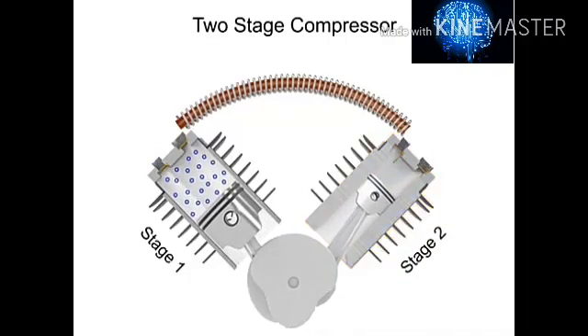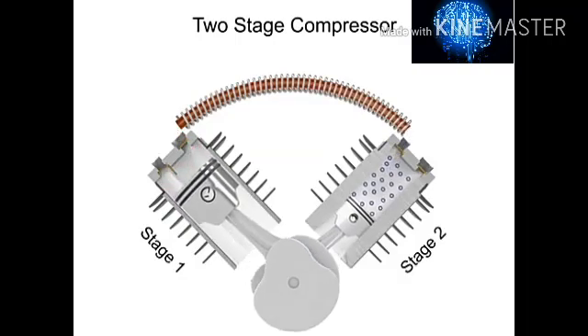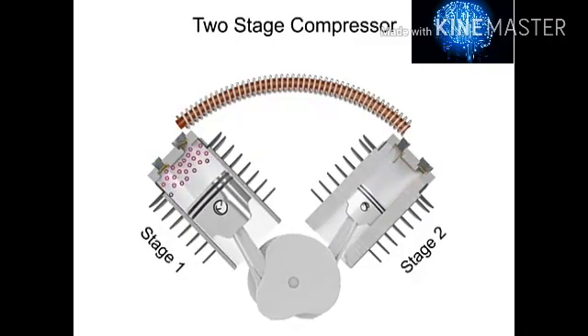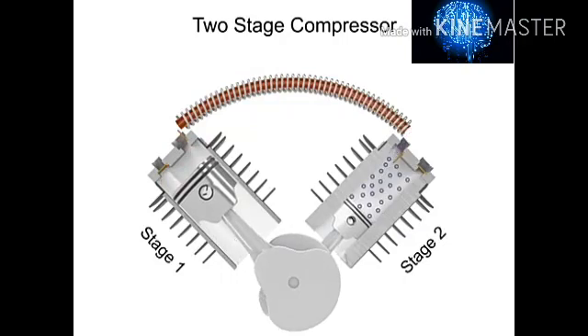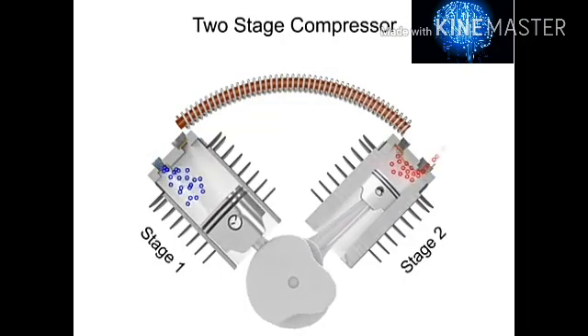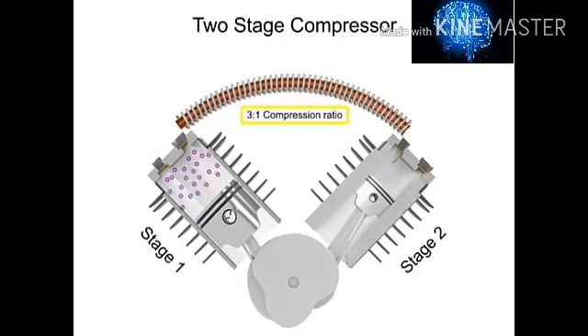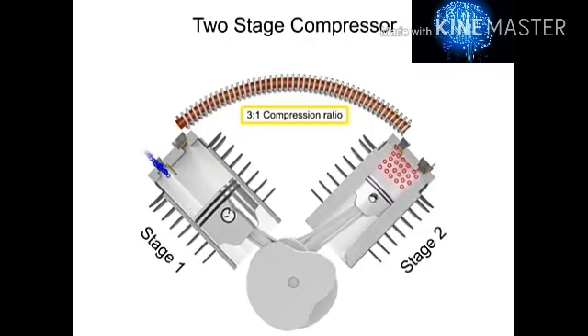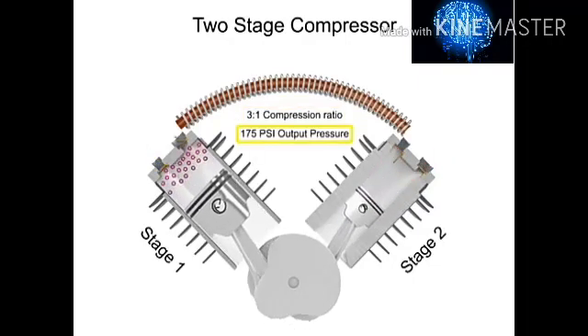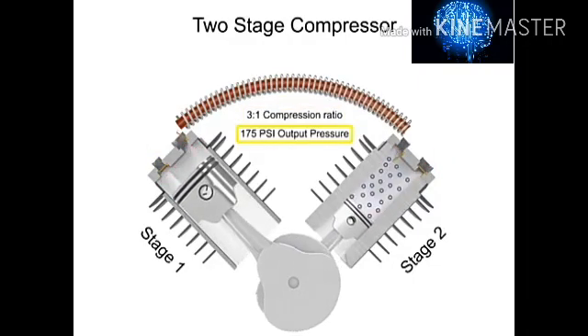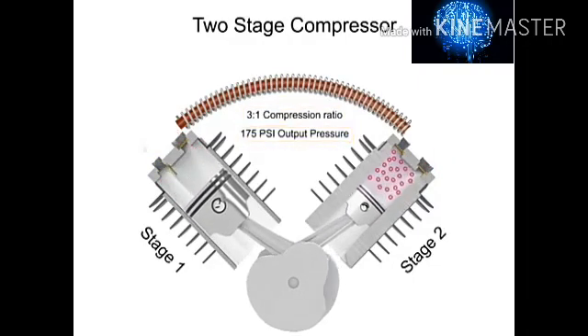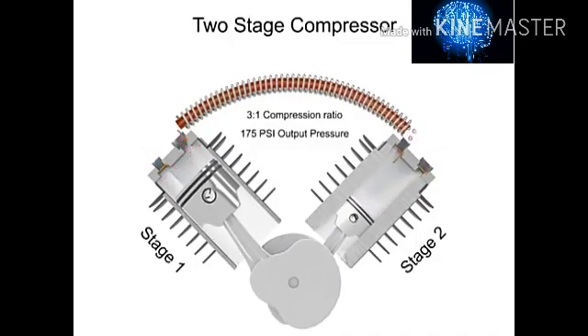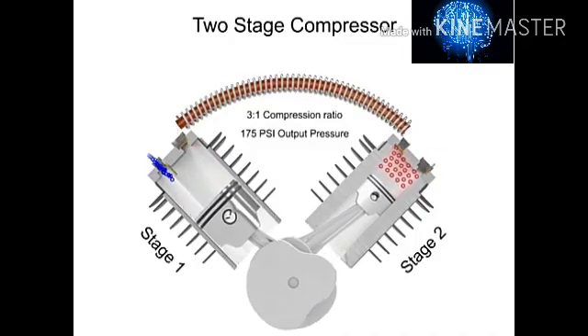The compressed air entering the second stage is sometimes called supercharged air. Two stage compressors have a compression range of 3 to 1 or even less per stage, but can operate up to 175 psi. They can also deliver more air at a higher pressure than single-stage compressors of the same horsepower.